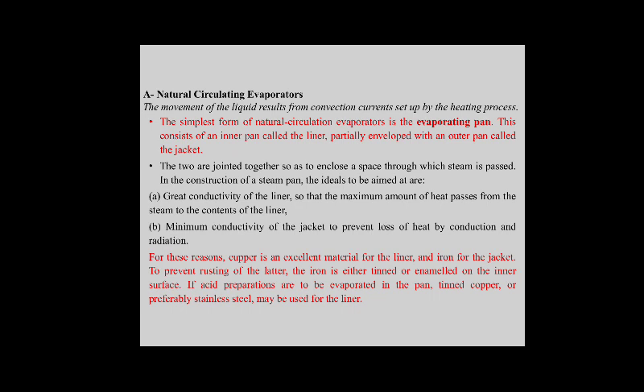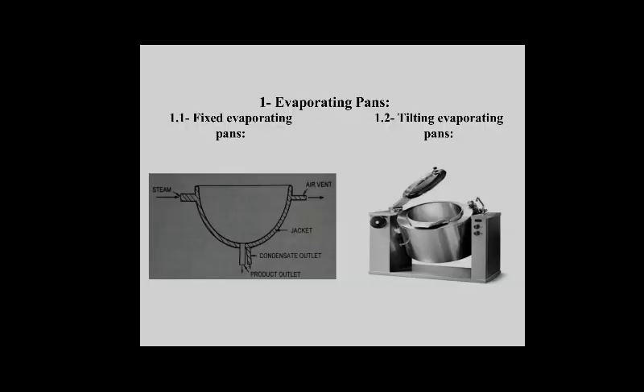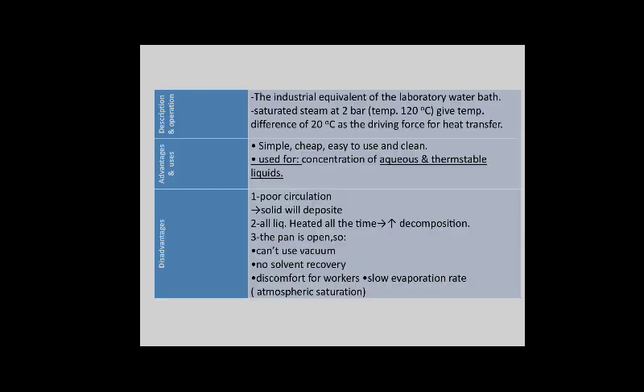The two are joined together so as to enclose a space through which steam is passed. The evaporating pan may be fixed or tilting. Advantages: it is simple, cheap, easy to use and clean, and is used for concentration of aqueous and chemically stable liquids. Disadvantages: poor circulation, solids deposit, all liquid is heated all the time increasing risk of decomposition, the pan is open so vacuum cannot be used, no solvent recovery if the solvent is expensive, worker discomfort, and slow evaporation rate.